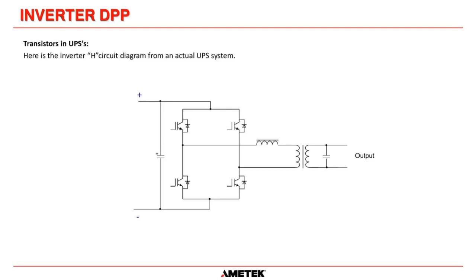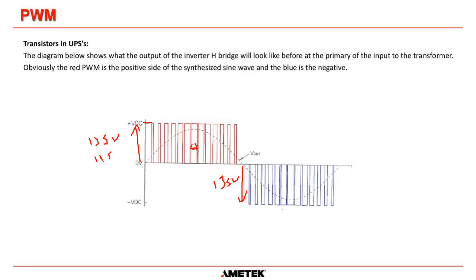I think the next slide explains it a little more. Remember, the DC amplitude is not going to change. If we had a fully charged battery, that's 135 volts DC, and that's still going to be 135 volts DC - all we're doing is adjusting these pulses. We can adjust those pulses for load requirements - remember we said the battery could go down to 105? Well, we can change the pulses to accommodate for that. We have much, much more control when you use pulse width modulation. The regulation on our systems with PWM is much better than the ferroresonant technology - the ferroresonant technology is good, just PWM is better.